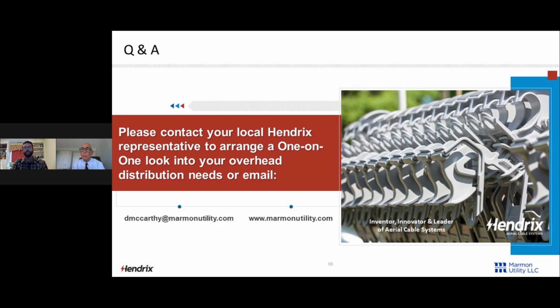This user was wondering, can a standard distribution pole be equipped with spacer cable hardware, or do you have your own standard pole lengths? Super question. No, I mean, we've used every type of pole on this planet in our working in 75 countries. I've seen every kind of pole there is. You can use a standard pole. The important thing is that we take a look at it and verify that it can handle the mechanical stress of those phase conductors. But yes, we do a lot of change outs from bare wire to spacer cable, on the same pole line with the existing poles.